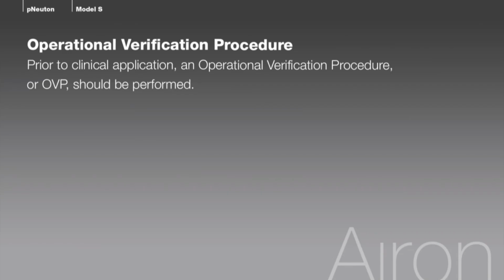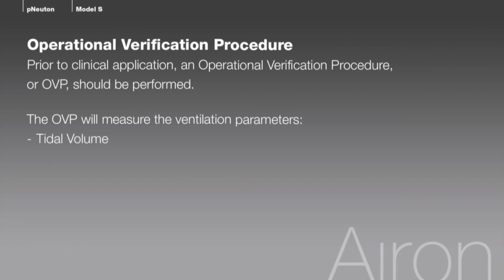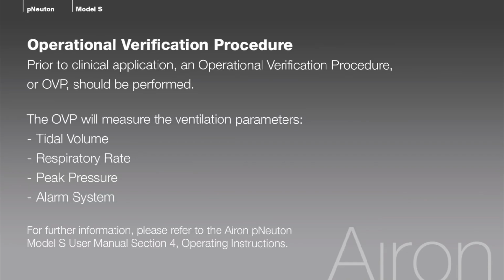Clinical application. One last step. Prior to clinical application of the pNeuton S ventilator, an operational verification procedure, or OVP, should be performed to validate the device's performance to specifications. The operational verification will measure the ventilation parameters, tidal volume, respiratory rate, peak pressure, as well as the alarm system. For further information, please refer to the User Manual, Section 4, Operating Instructions.